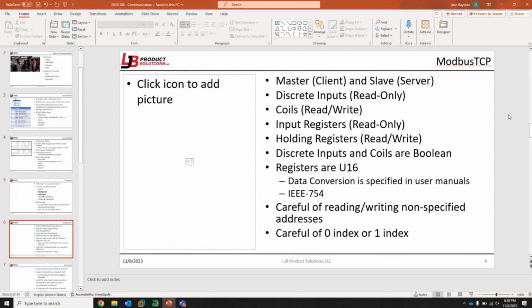A lot of them, I know you're big with Kollmorgen. Kollmorgen, everything in their Modbus was two data registers regardless of what the actual value was. And that would kind of throw us off because we didn't know any better. I didn't know any better when I was first starting to do this stuff. So I'm like, yeah, you read two, what the heck? And you've got to learn how to put numbers back together and get them in the right order.